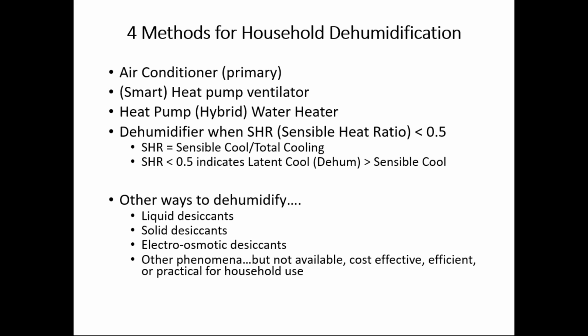And then finally, when conditions dictate, and basically those conditions are when the sensible heat ratio, the ratio of cooling needed to change the temperature in the house, basically the sensible cooling, to the total cooling, which is the sensible plus the latent, the moisture. When the latent cooling becomes more than half of the cooling load, this is when dehumidifiers especially are needed, and Miami, as we'll see, is a good example of that. So we'll look at that further in this example. For sure, there's other ways to dehumidify, but these are not on the market or not readily usable by residents.